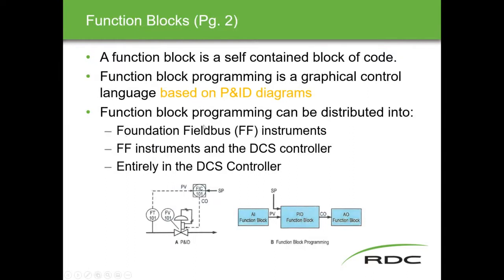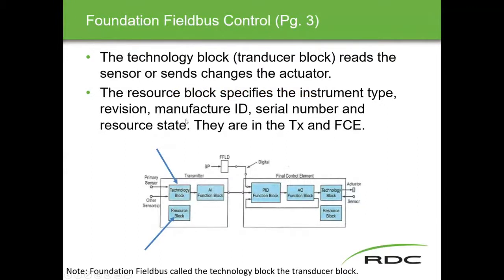This covers the gamut in terms of how you can integrate Foundation Fieldbus — from exclusively Foundation, to a mixture of Foundation and other devices, to what is probably more common: entirely within the DCS controller. Function block programming takes these little blocks found in a library, you drag one into a screen, connect and configure them — that's the general idea. Looking at these three methods, we'll spend a second on what it looks like if all control is done within Foundation devices, then a combination, then everything in the controller.